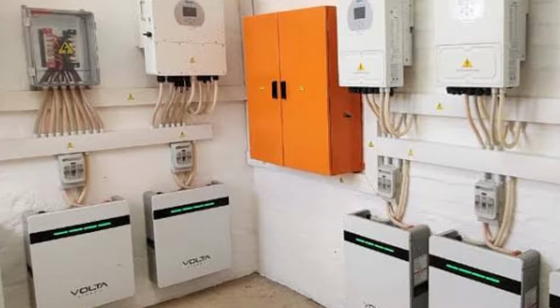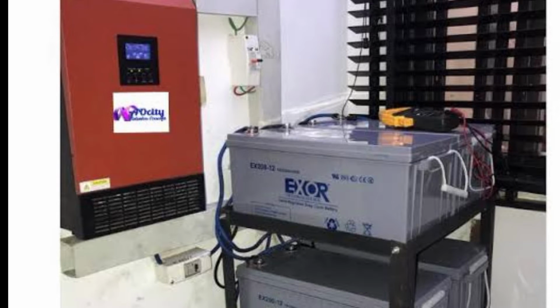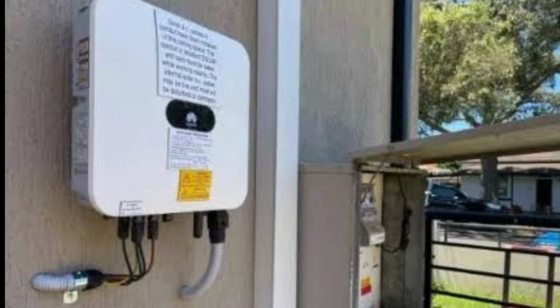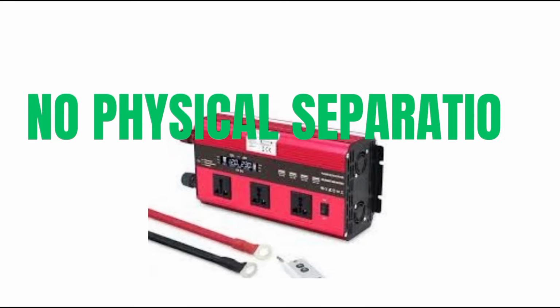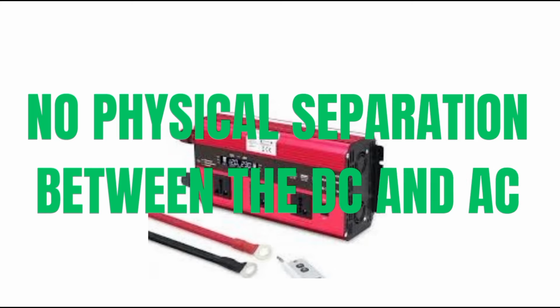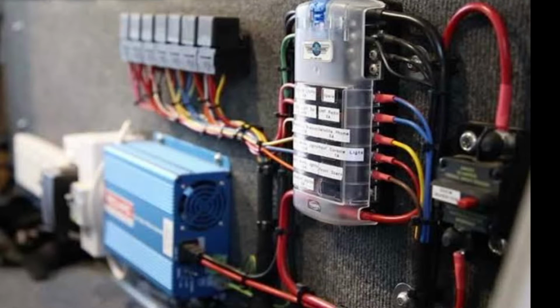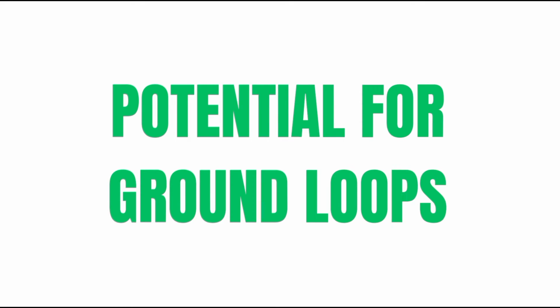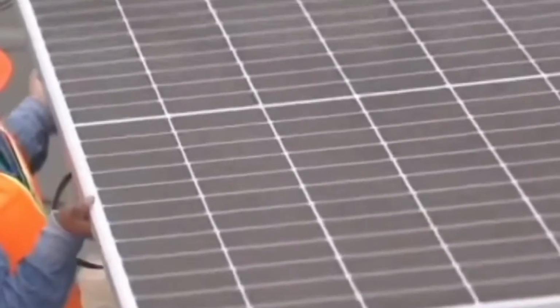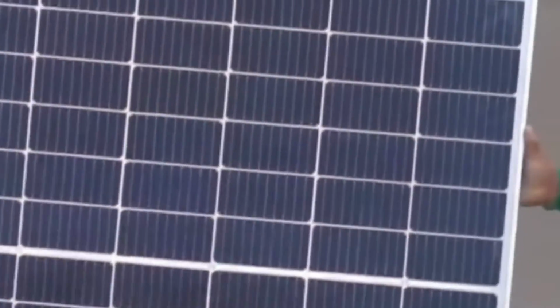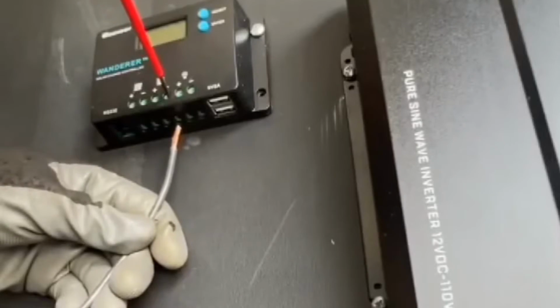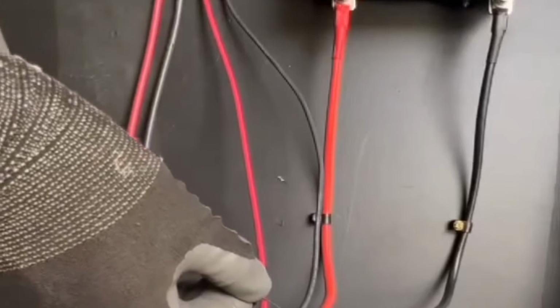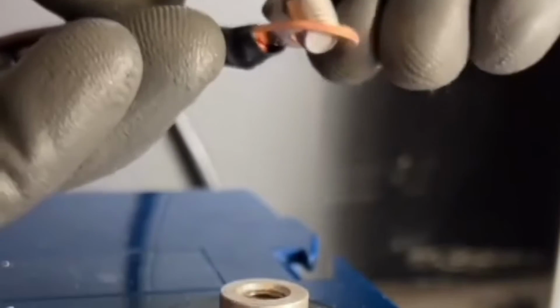But here's the catch: because they lack that big, beefy transformer, transformerless inverters don't have that inherent galvanic isolation. This means there's no physical separation between the DC and AC sides, which can be a concern for safety, especially if you're not careful with the installation. Without that isolation, there's a potential for ground loops and other electrical gremlins to wreak havoc on your system. So if you're going with a transformerless inverter, it's crucial to pay extra attention to grounding and safety measures during installation. Make sure you have a qualified electrician handle the job to avoid any unwanted surprises later on. Trust me, dealing with electrical problems is about as fun as a root canal. You want to avoid it at all costs.